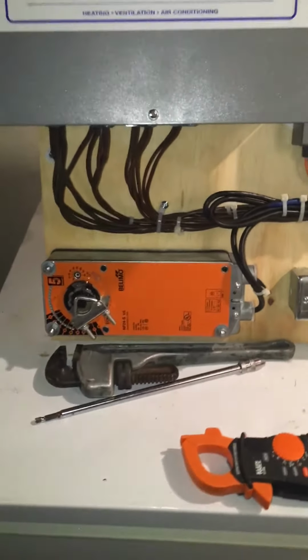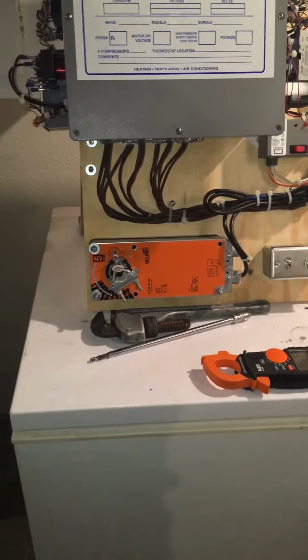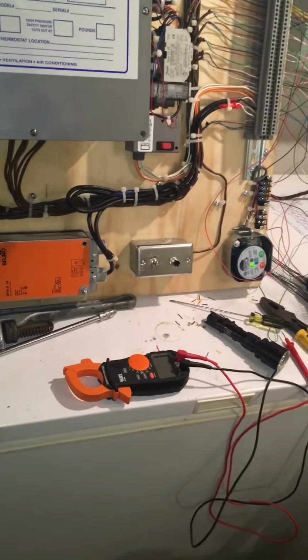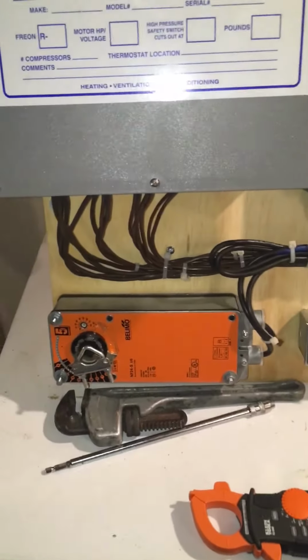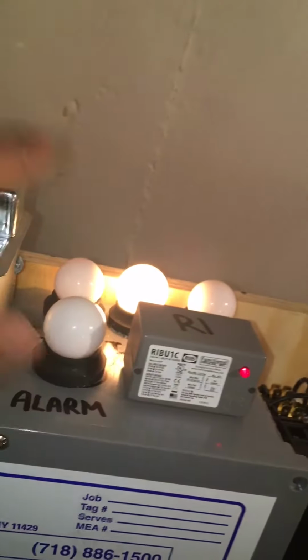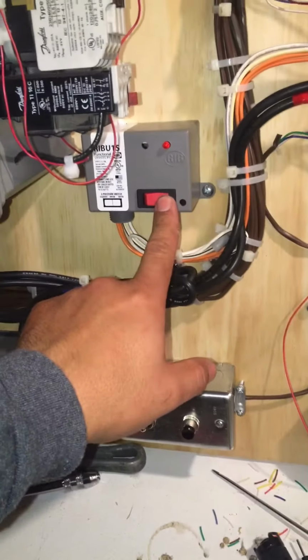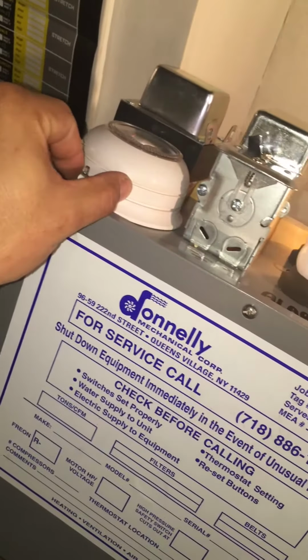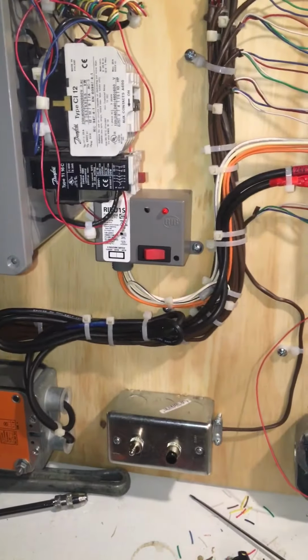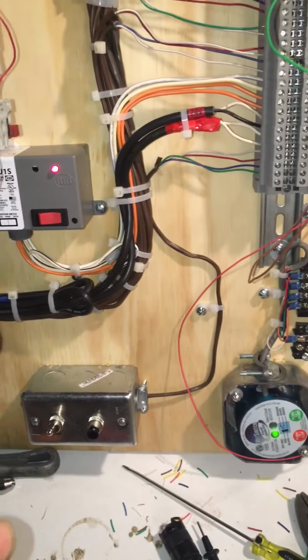So as this continues to open up, we just wait for the light to turn on upstairs. There we go. Relay 1 turned on. Indoor fan just turned on. Now, as you see, I got the HOA switch in the auto position. Put this into cooling off the T-stat. That just happened. There you go. Rib relay in the auto just turned on the condenser water pump contactor.